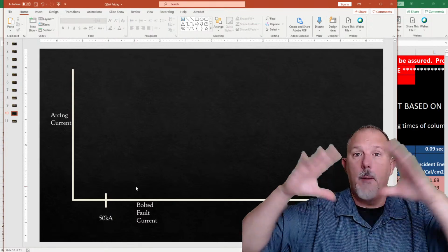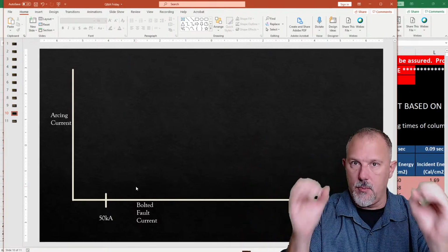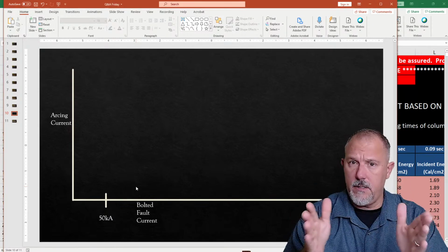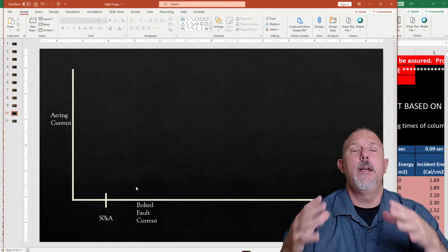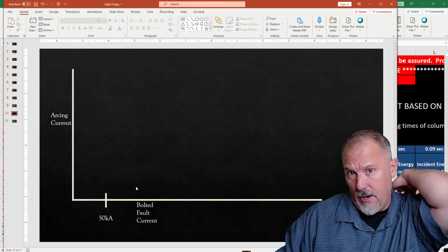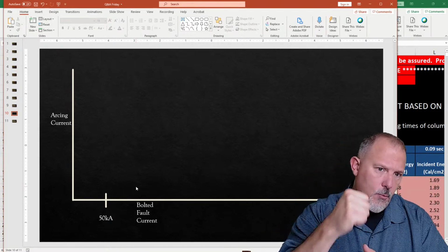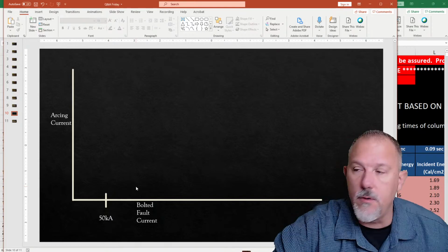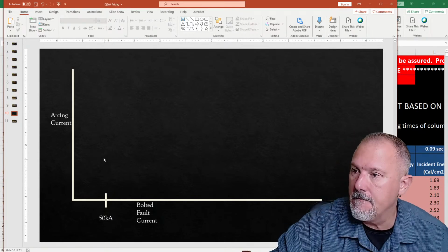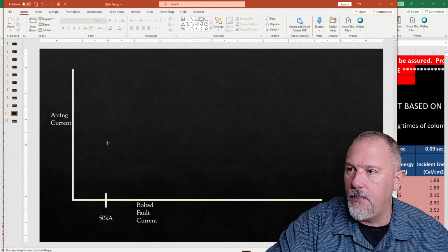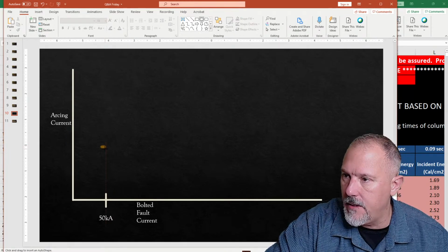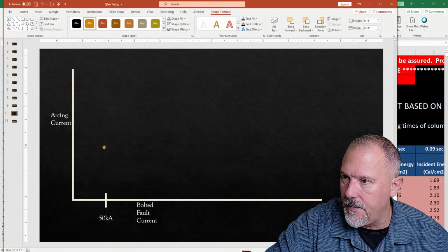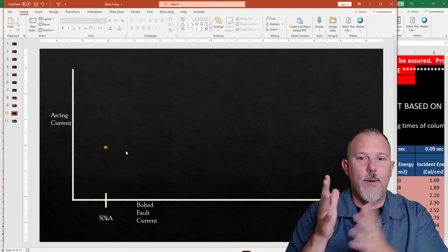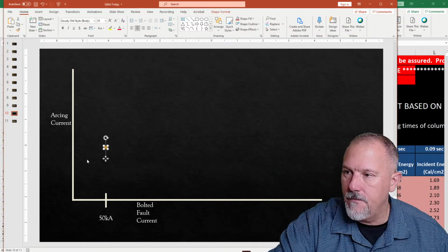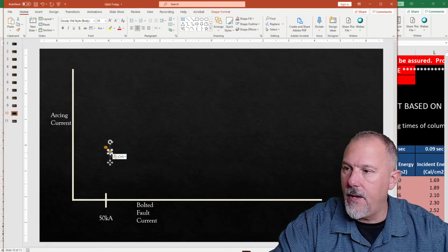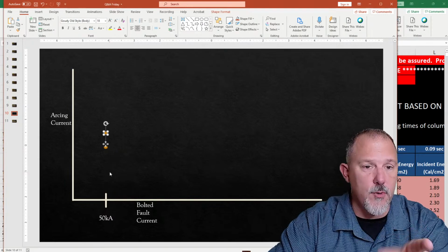He has a box that basically has three electrodes, spaced a distance away, all that jazz. He puts an ignition wire across all three of those. Boom, we close into that, and kaboom, we get a fault. We get an arc flash. And then he records a data point. There is a data point. Then what does he do? He says, set it up again, and we get another data point for that same bolted fault current value.